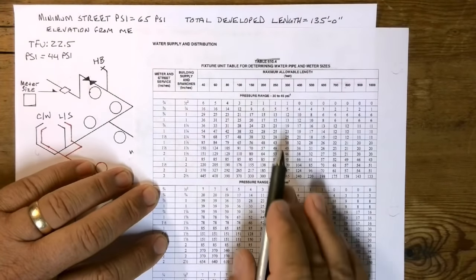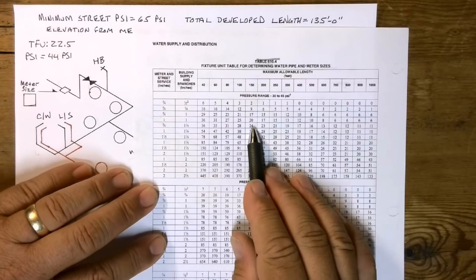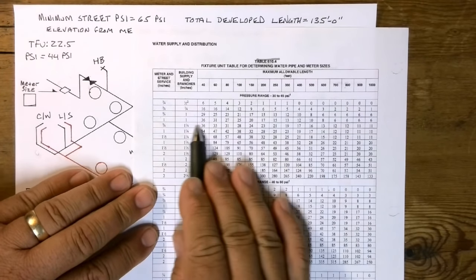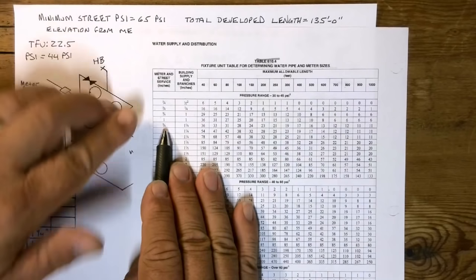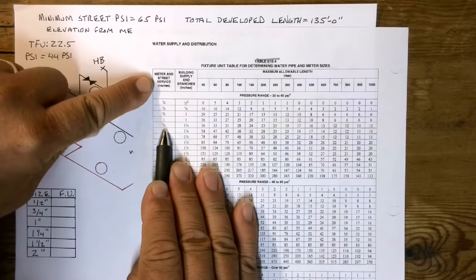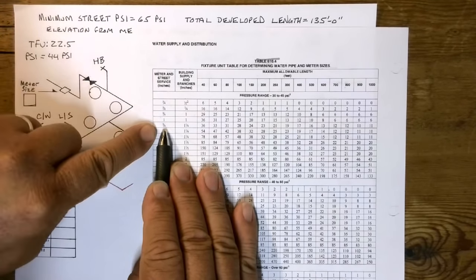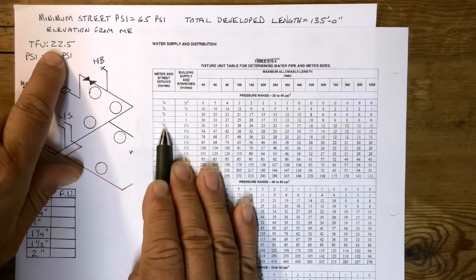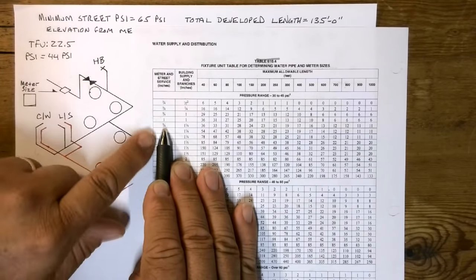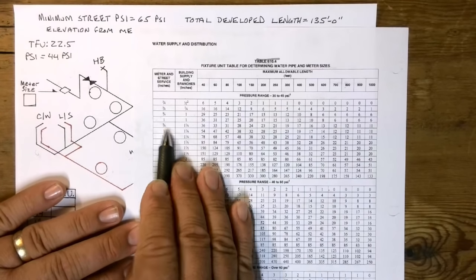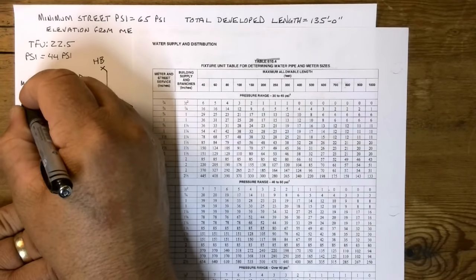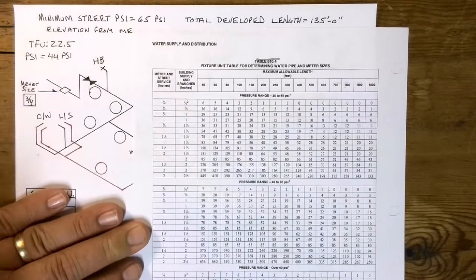Now, like I said, we're sitting at 24 fixture units. We come across here all the way over to the left because the first thing we need to do is find out what our meter is. So the meter, based on 22.5 fixture units, my meter size is 3/4. Okay? So we put 3/4 right there for the meter size.